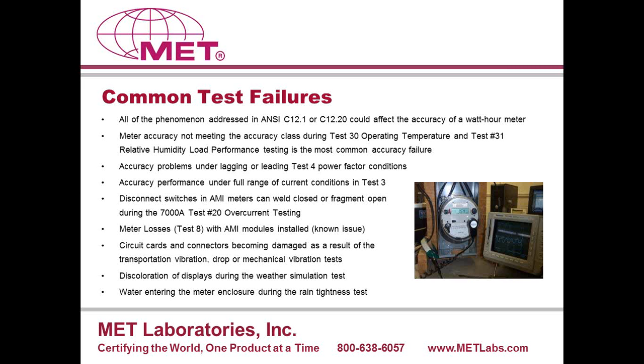Metering losses, again, I mentioned that the standards were written to address the meters only. Now that the meters have wireless modules installed, many times the meter loss testing will not comply because of the additional load draw due to those AMI modules installed.